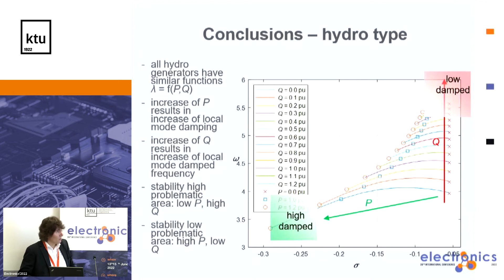So this gives a very good answer. If somebody is operating at some nominal operating point somewhere here, and the system starts to oscillate, if he wants to increase the damping of oscillation, what he has to do is reduce the reactive power and increase the active power. This is an important conclusion.